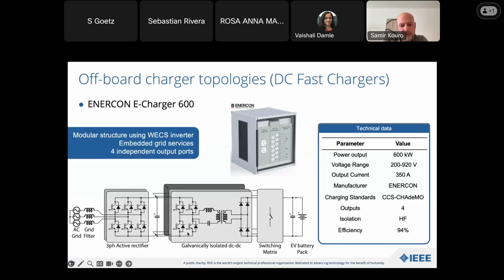This is followed by galvanically isolated high frequency converters, as you can see here, with a passive output. Because of this, it's not bidirectional capable. Again, because all the different channels are galvanically isolated, we can now, with the switching matrix, connect them in parallel or in series, depending on if we want 400 volt or 800 volt batteries.